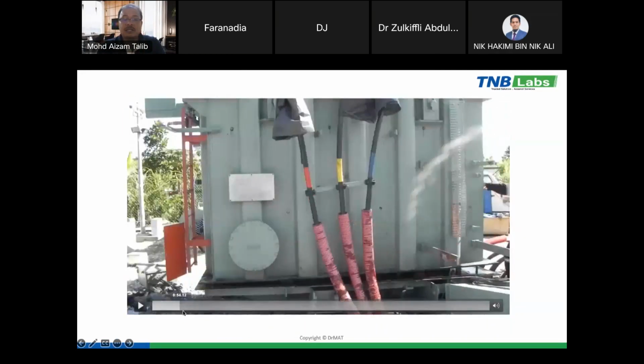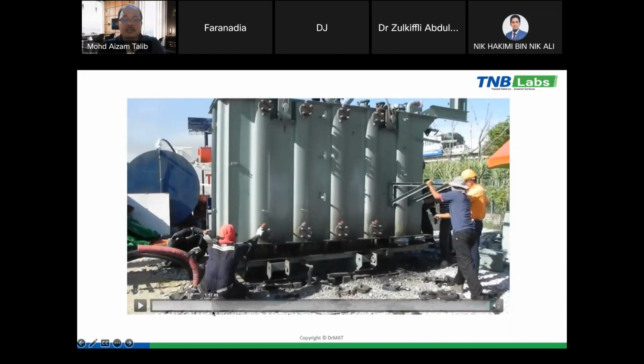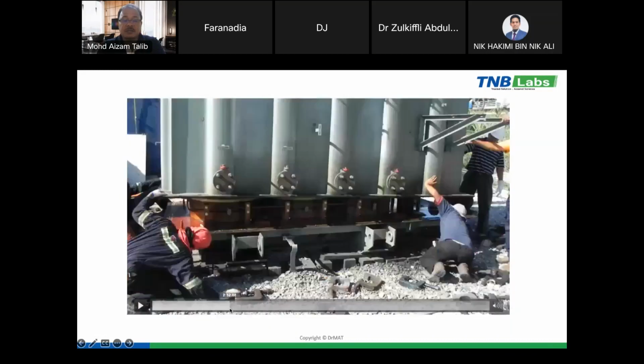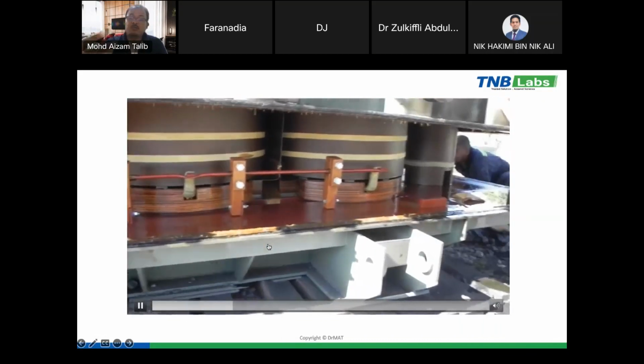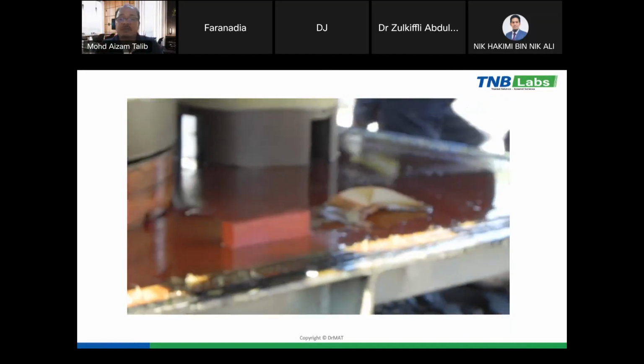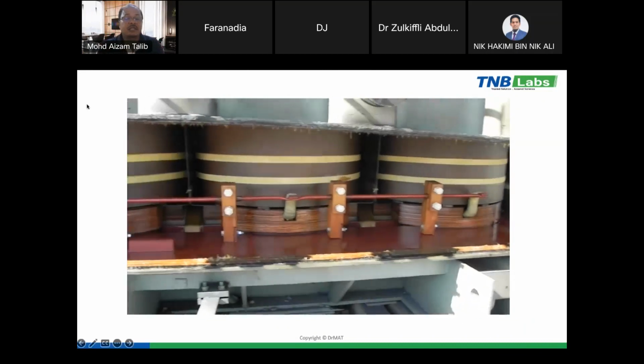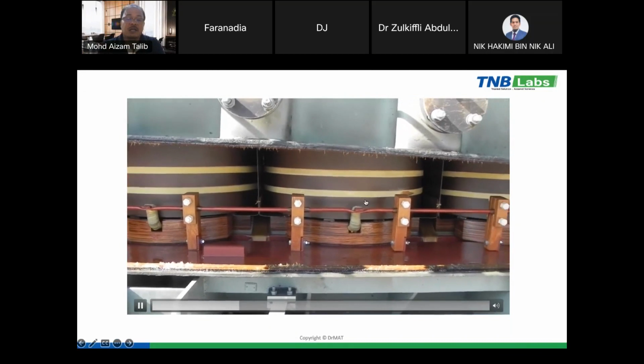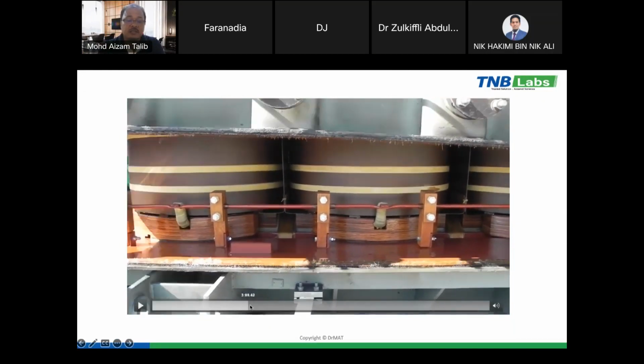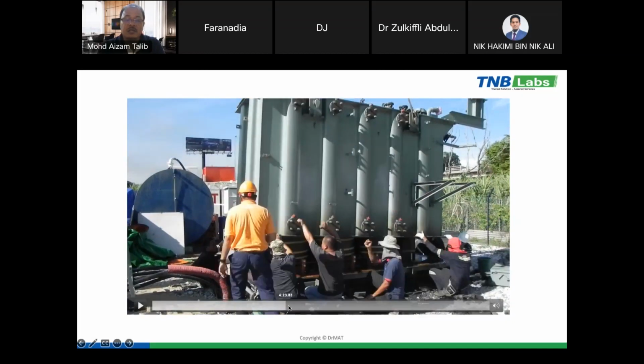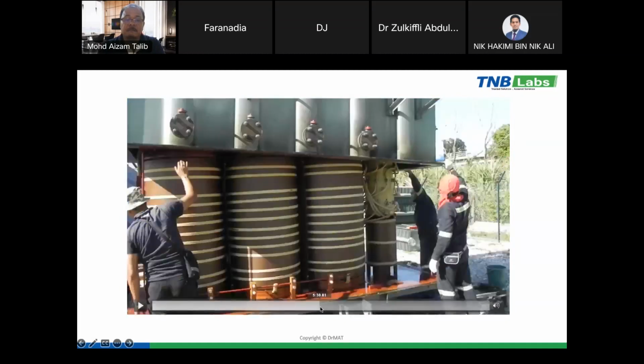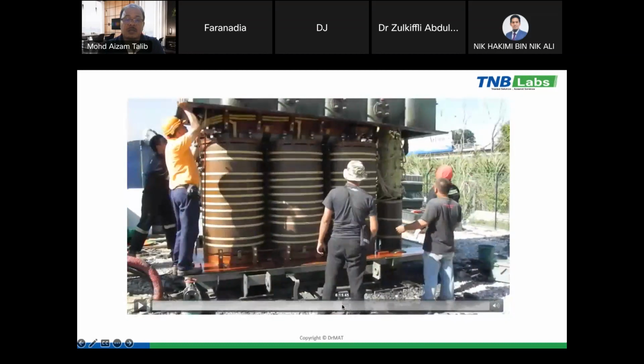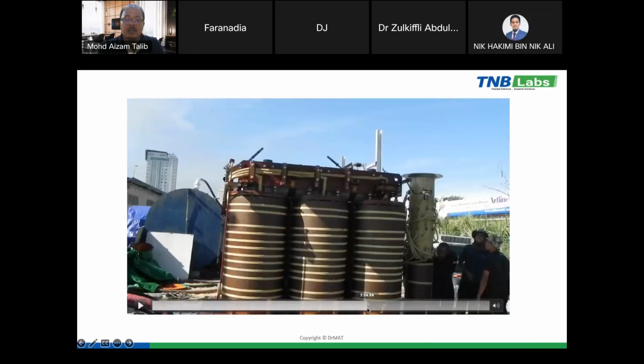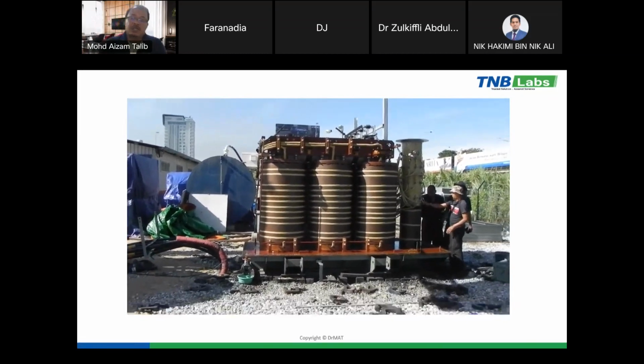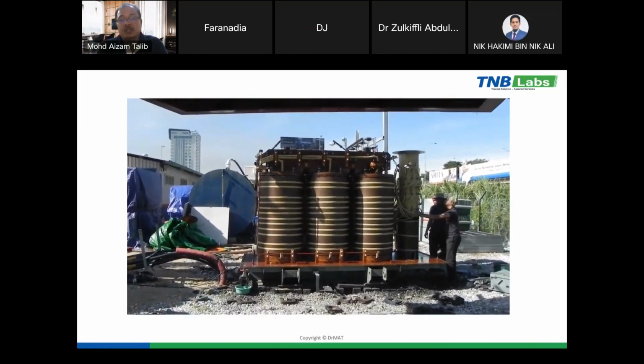Okay, I need to speed up. So we untank the transformer tank. Here we untank slowly. We remove all the oil from the transformer, and then we open the transformer tank. And then we can see the transformer winding, here the red phase, yellow phase, and the blue phase. So the tank is completely removed. And then on the left, the transformer winding and also the tap changer.